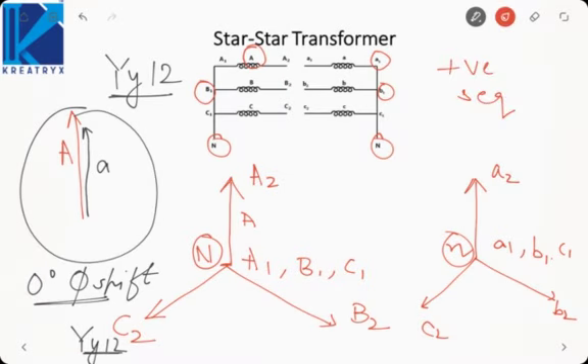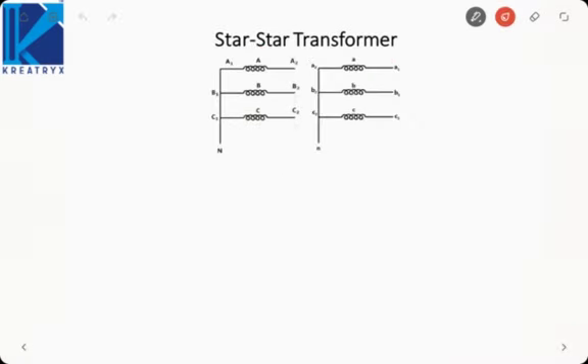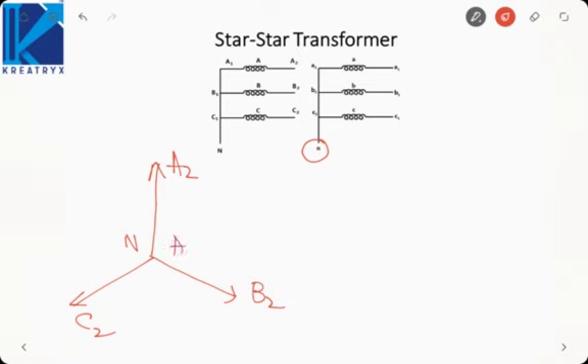Now let us change the secondary connections and try to determine the phase shift. So here I have connected A2, B2 and C2 to the neutral terminal and A1, B1, C1 are free. So again first we will draw the primary phasor. This is A2, then B2, then C2. This will be my neutral point. Now this phasor is going from A1 to A2, but here we are taking output from A1. So we will draw a phasor from A2 to A1. If A1 to A2 is vertically upwards, A2 to A1 will be vertically downwards. Now B2 to B1 will be something like this, opposite to this.